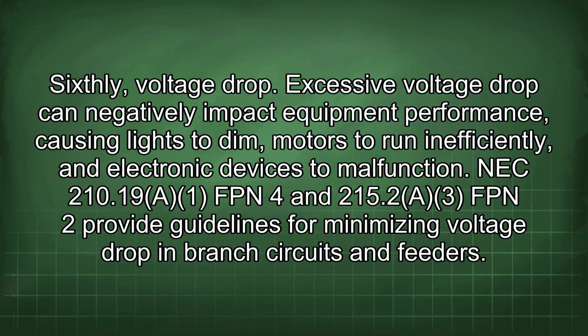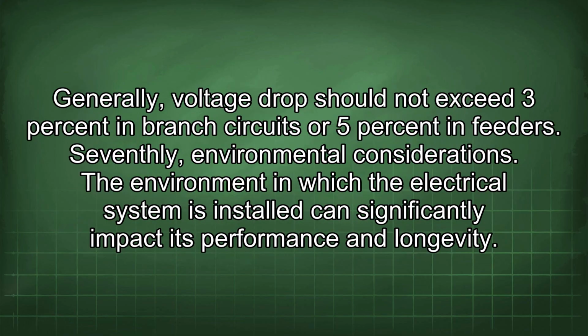Sixthly, voltage drop. Excessive voltage drop can negatively impact equipment performance, causing lights to dim, motors to run inefficiently, and electronic devices to malfunction. NEC 210.19(A)(1) FPN 4 and 215.2(A)(3) FPN 2 provide guidelines for minimizing voltage drop in branch circuits and feeders. Generally, voltage drop should not exceed 3% in branch circuits or 5% in feeders.